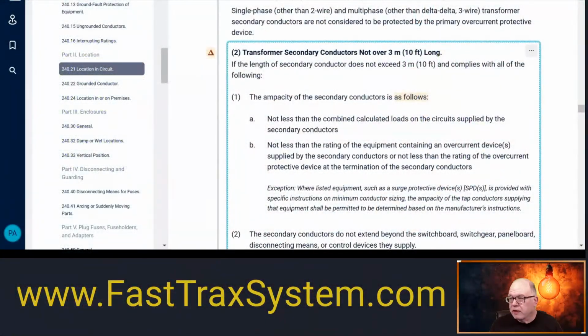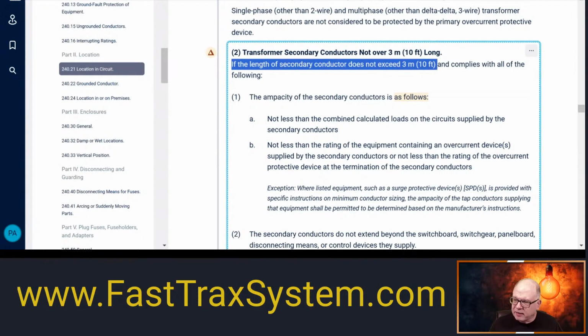All right, so these secondary conductors. It says, if the length of the secondary conductor does not exceed 10 feet and complies with all of the following. So this is not a partial rule here. You've got to comply with everything in order to do this tap rule. And this tap rule, I catch myself doing it too. This secondary, see how easy that happens?